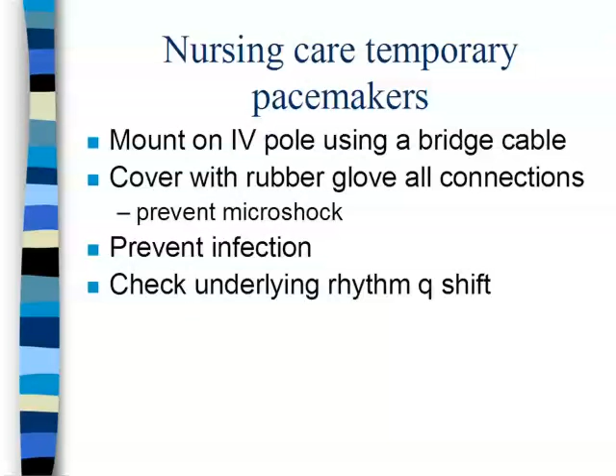If you see nothing in one screen across, that's long enough to say they don't have an underlying rhythm yet. Take your finger off the generator. You need to assess for any pacing abnormalities, such as failure to sense or failure to pace. And there are examples of malfunction on page 505. There are rhythm strips that show the pacemaker spike on page 504.